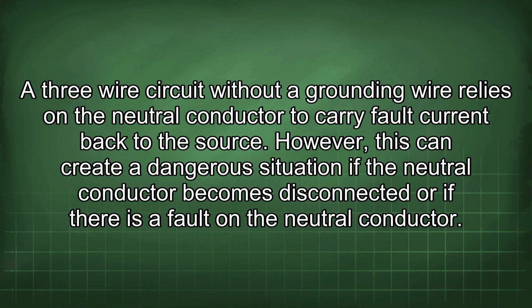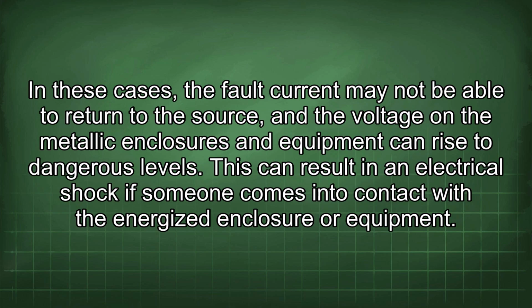A 3-wire circuit without a grounding wire relies on the neutral conductor to carry fault current back to the source. However, this can create a dangerous situation if the neutral conductor becomes disconnected or if there is a fault on the neutral conductor. In these cases, the fault current may not be able to return to the source, and the voltage on the metallic enclosures and equipment can rise to dangerous levels. This can result in an electrical shock if someone comes into contact with the energized enclosure or equipment.